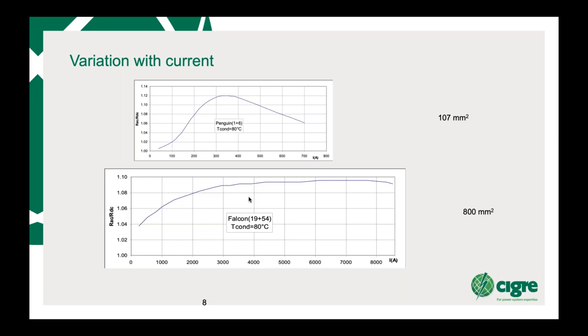So you'll get a current going in one direction in the first layer, in the second layer it's going in the other direction, so it cancels it, and in the third layer it goes the same as the first layer. So you'll then find that there is a slight increase, and that goes up to around 10%. But again, if you're looking at around 4 amps per square mil, that's where you need to start worrying about it.